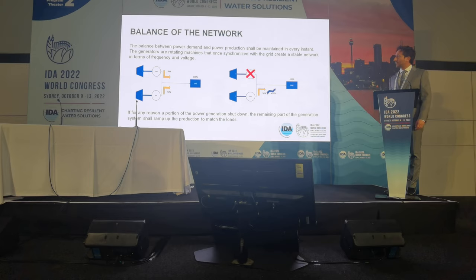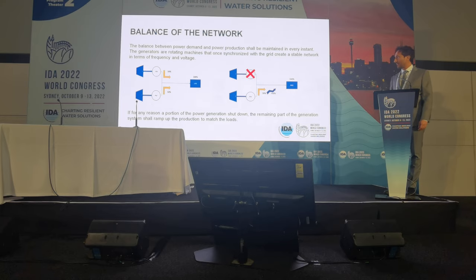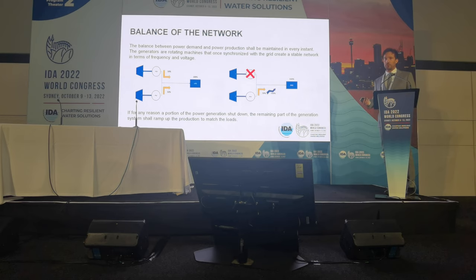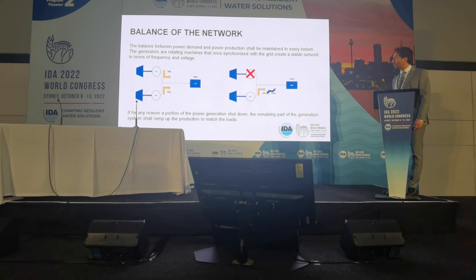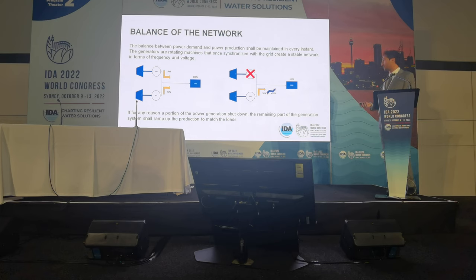To balance the network, we have to remember that production should match consumption at every instant. If we lose part of the production, we have to recover it with the spinning reserve — even if a power plant is not working at full capacity, it must ramp up as fast as possible to catch the load and maintain frequency and voltage in the network.